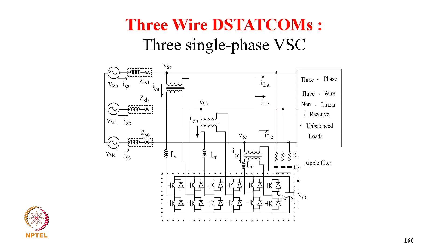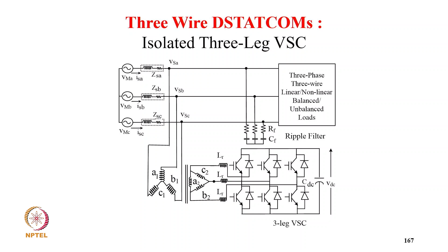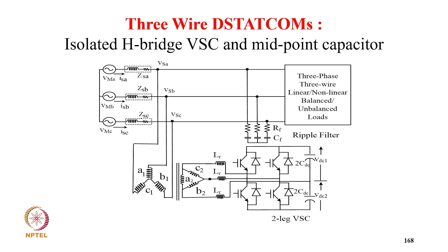And this is again an isolated topology with a star delta transformer and a 3 leg converter. This topology is also quite popular because you are designing the power electronics at low voltage while your power circuit is quite high voltage. So in that case, this is quite useful. And this is then again isolated, also with 2 leg. Again, the midpoint is taken as a return path to one particular phase.